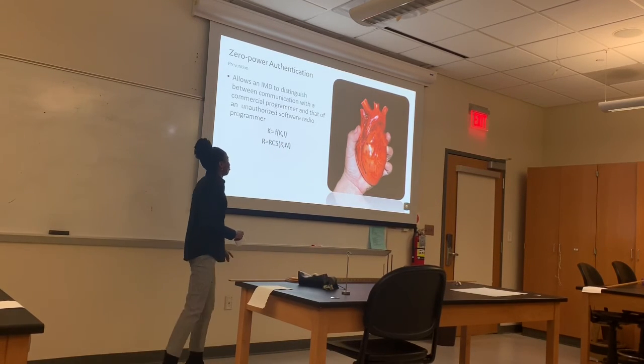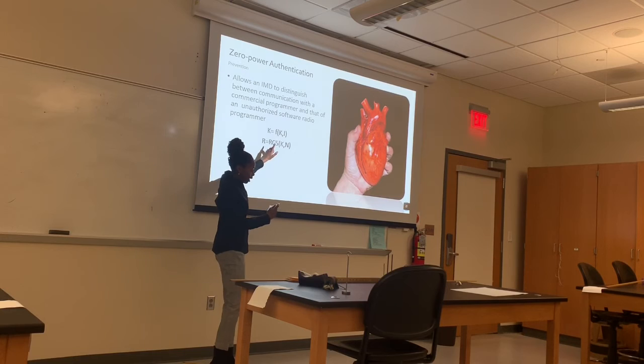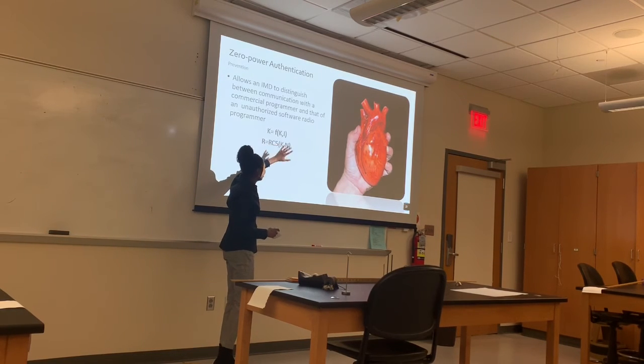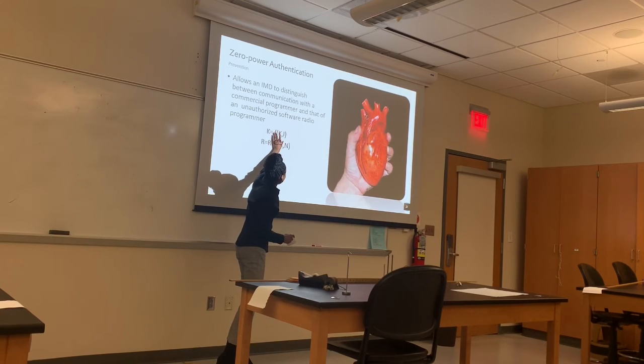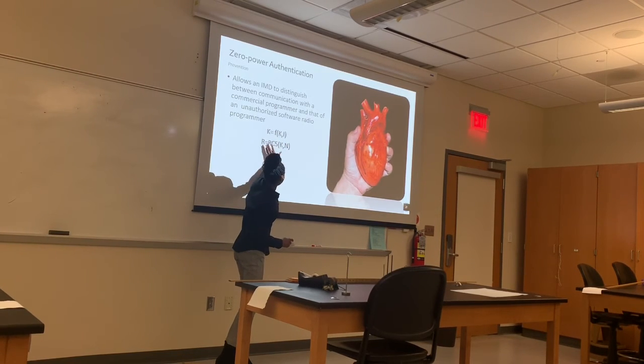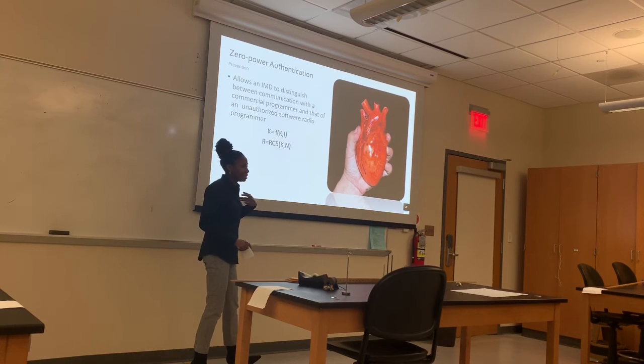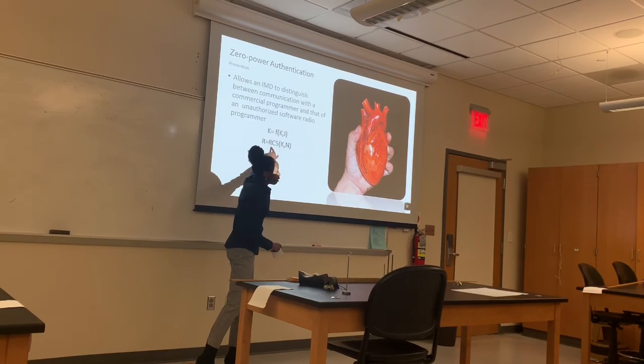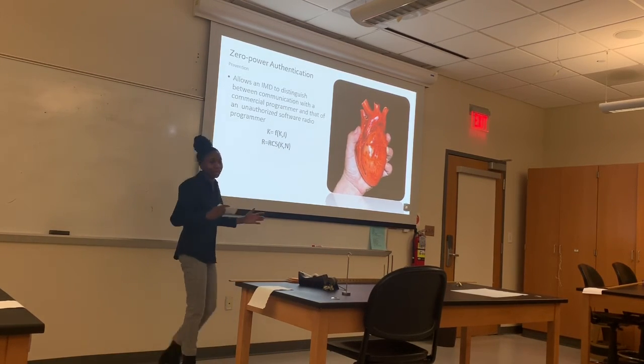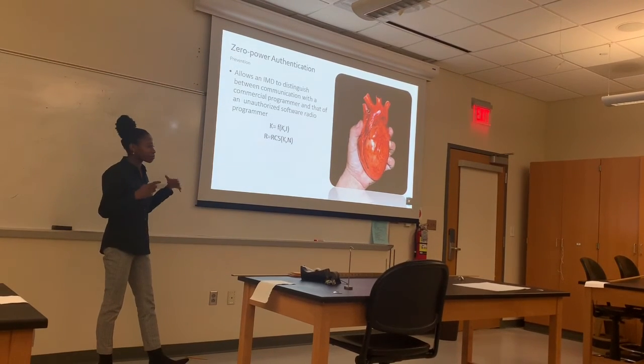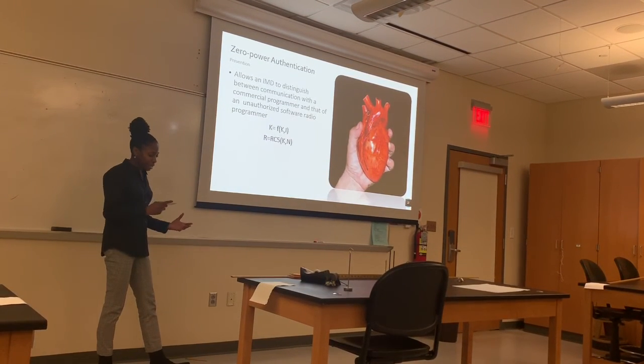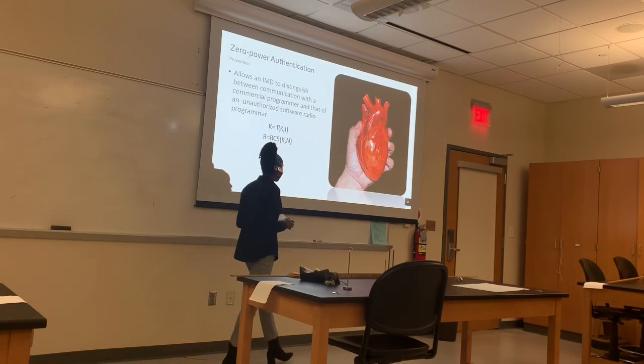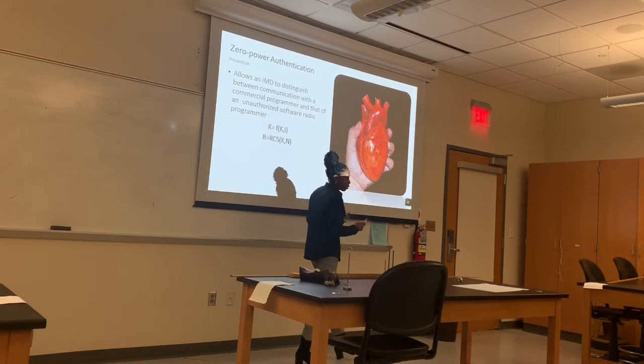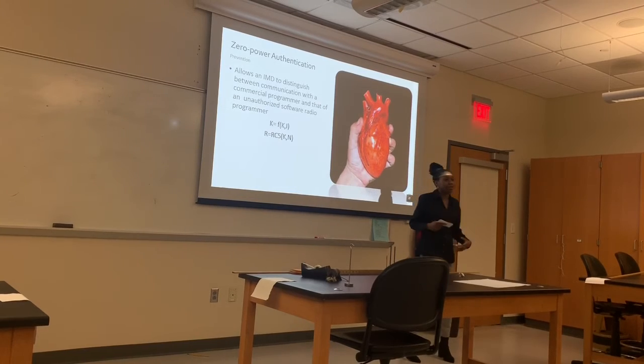And then the commercial programmer is supposed to respond with its programmer master key, which will allow it to calculate this number, which will then allow it to calculate this number, and then once the ICD gets this number from the ICD programmer, it will then allow it to change its therapies. So the point is that if it's not a commercial programmer, it will not have the programmer master key, and then the therapies within the ICD will not be able to be altered.